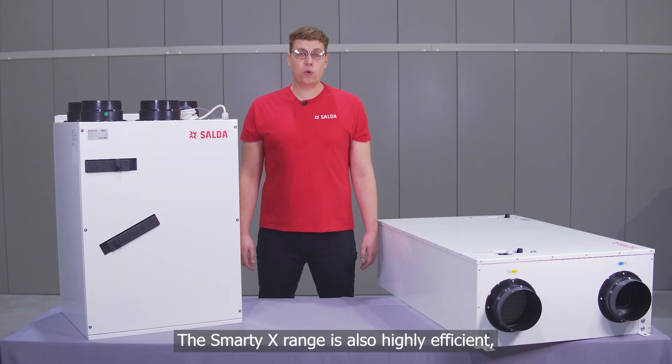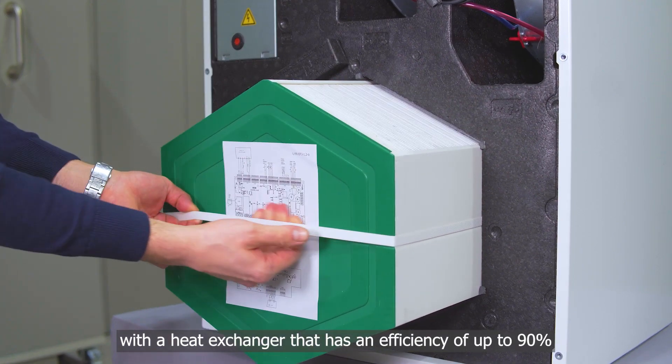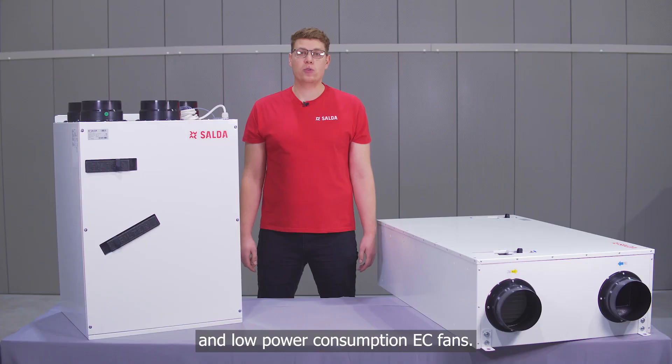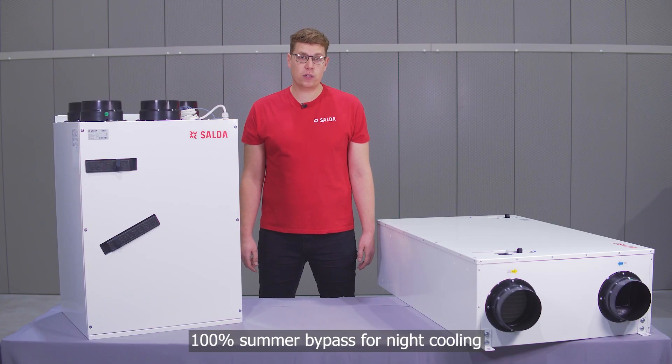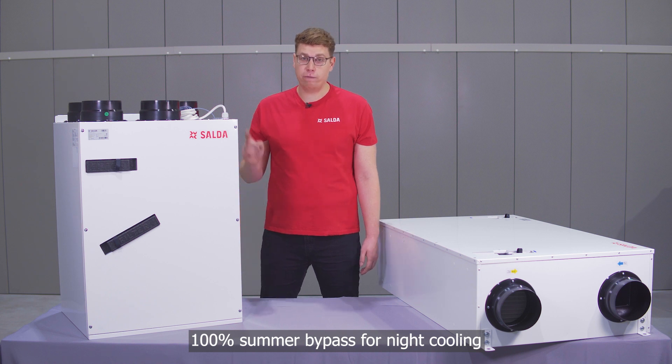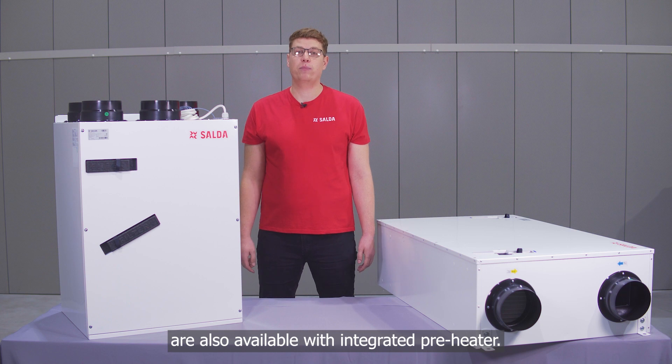The Smarty X range is also highly efficient, with a heat exchanger that has an efficiency of up to 90% and low power consumption EC fans. The motorized bypass damper allows 100% summer bypass for night cooling, and vertical versions of Smarty X are also available with an integrated pre-heater.